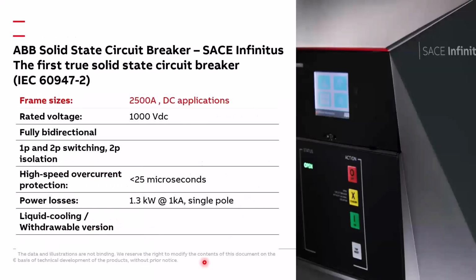Here are the main characteristics of this circuit breaker. So far the frame size is 2500 amp at 1000 volt, but we are still thinking about frames with a higher value of current and also with a lower value, in order to be able to enable the total DC distribution, also considering a feeder having a lower current, for example, supplying DC chargers.